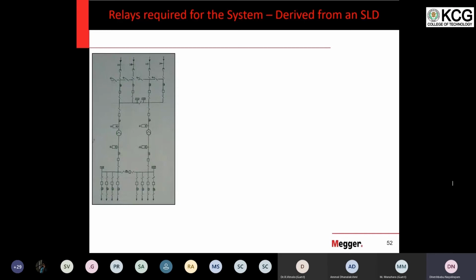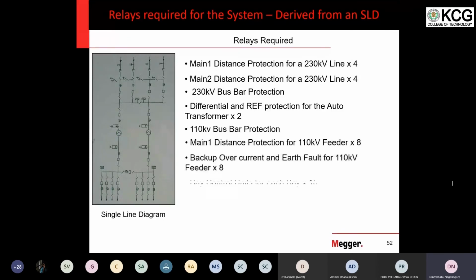This is the single line diagram which we remembered. 4 incoming 230 kV lines, 2 autotransformers and 8 outgoing 110 kV lines. These are the protection functions required to protect this substation. For the 230 kV lines, you need main 1 and main 2 distance, differential and restricted earth fault; 110 kV busbar protection, distance protection for feeders, backup overcurrent and earth fault, and there are 15 bays. Therefore, 15 BCUs. Now, what is a bay? This is a bay, what I show here with the arrow mark.